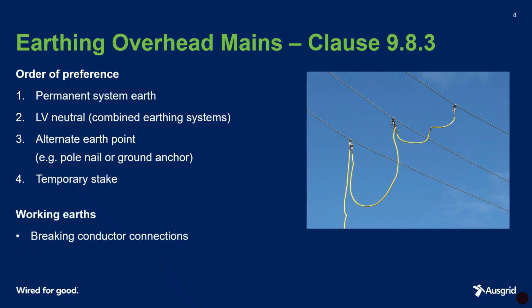Also, in Clause 9.8.3, the access permit recipient is now responsible for the installation of working earths where the work involves the breaking of conductor connections that would otherwise result in sections of overhead mains no longer being earthed and short-circuited.